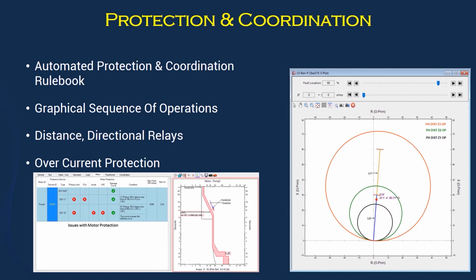Also, the ability to simulate sequence of operations by graphically showing trip devices operate in the event of a fault. This provides the protection engineer with the ability to visualize the sequence of operation based on a single line to ground fault, a three-phase fault, a line-to-line ground, etc. And it supports from distance and directional relays to overcurrent and thermal devices.